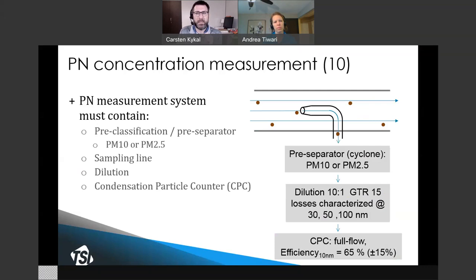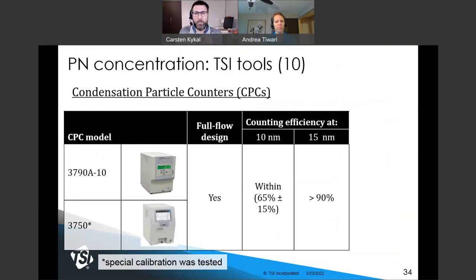Section 10 also provides requirements for the CPC. First, it must be a full-flow CPC, meaning all of the flow entering the instrument inlet must go through the optics. Secondly, the counting efficiency must be such that it can detect 10 nanometer particles successfully 65% of the time, plus or minus 15%. Further, the CPC must detect 15 nanometer particles successfully more than 90% of the time. TSI has been designing and manufacturing CPCs for nearly four decades and has two models suitable for brake wear measurements: the 3790A-10, an older model already calibrated at the sizes required by the PMP protocol, and the newer 3750. Both are full-flow CPCs that meet the counting efficiency requirements.